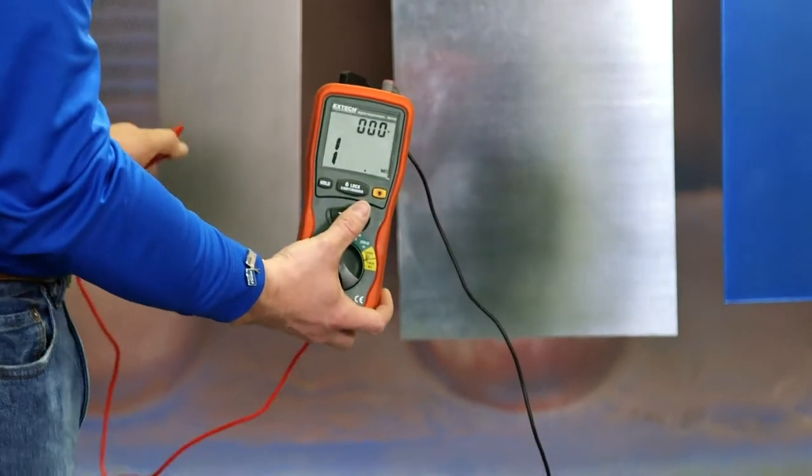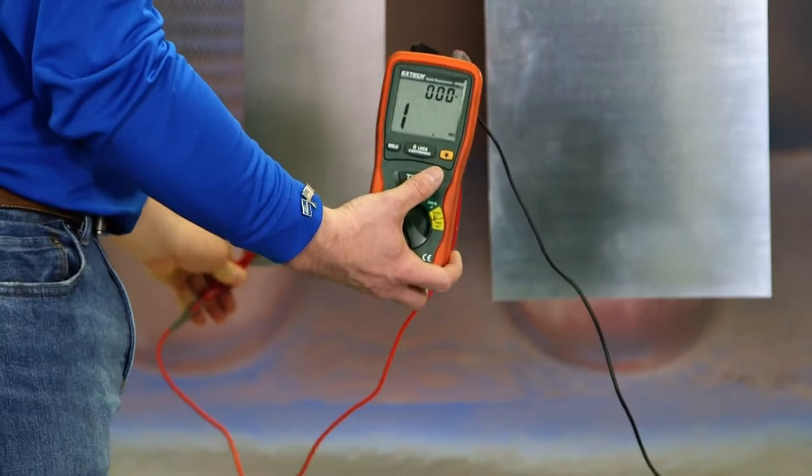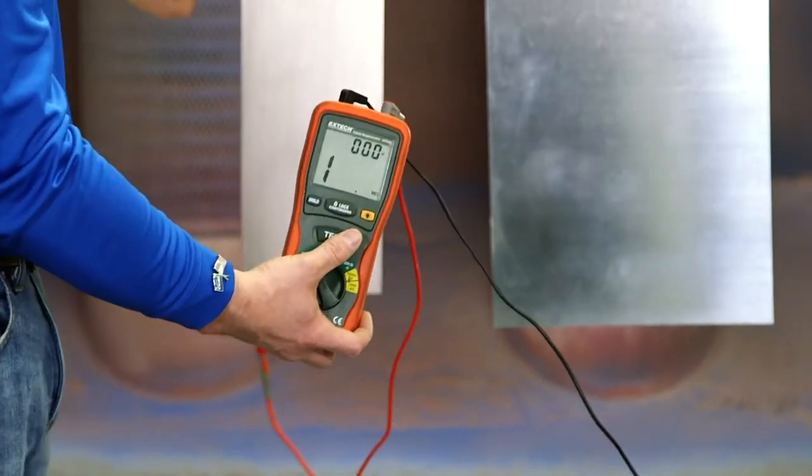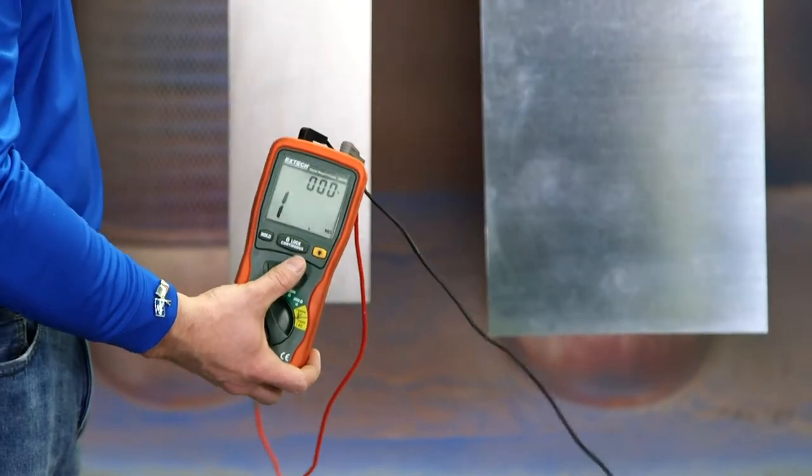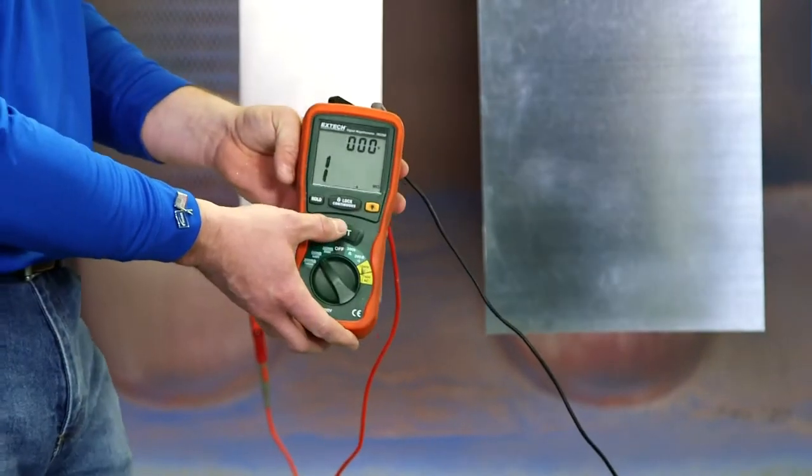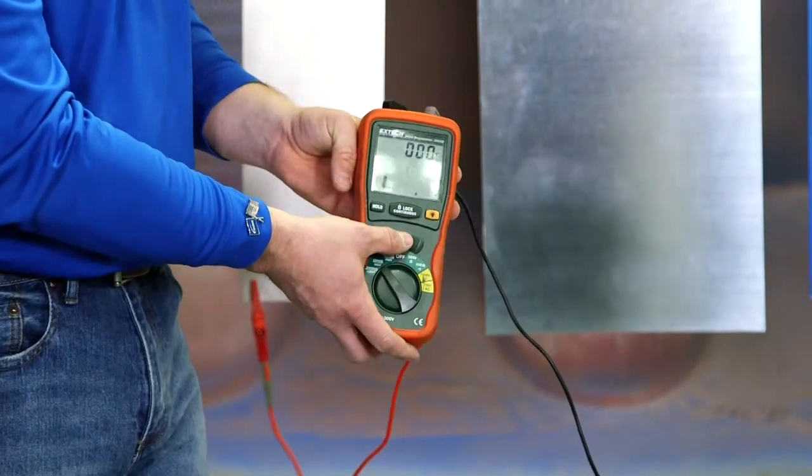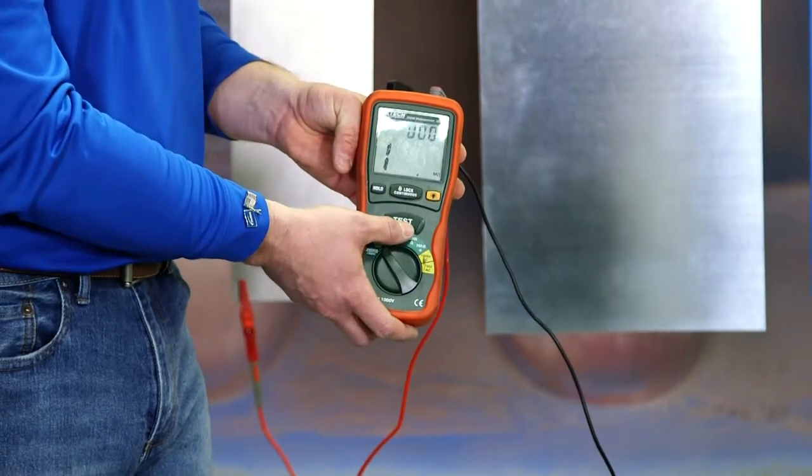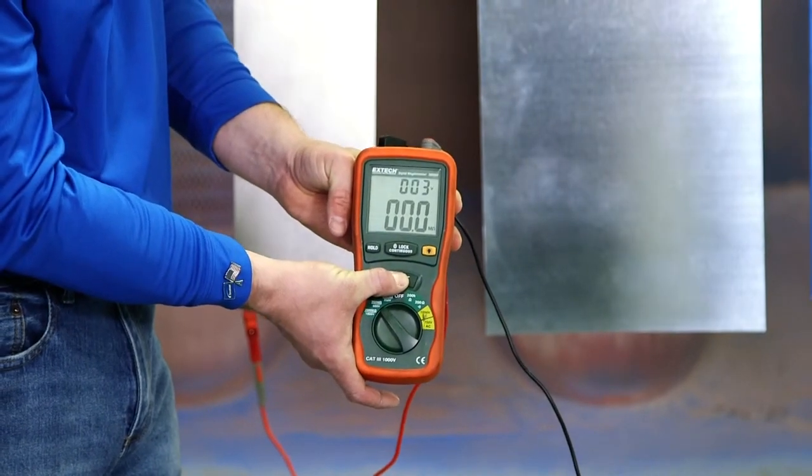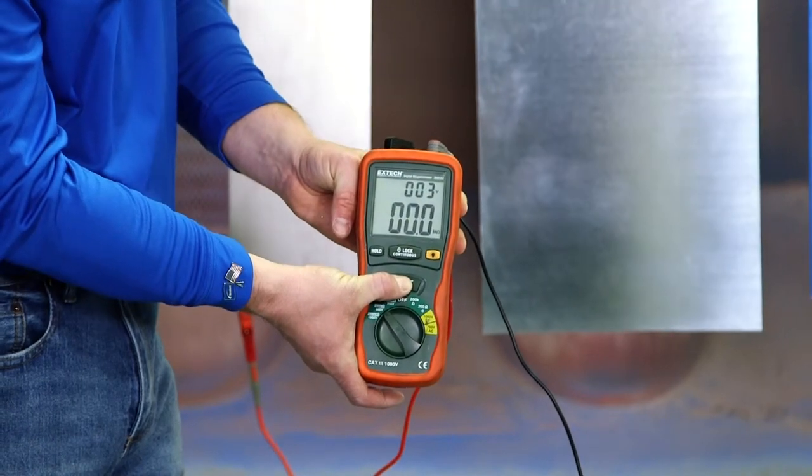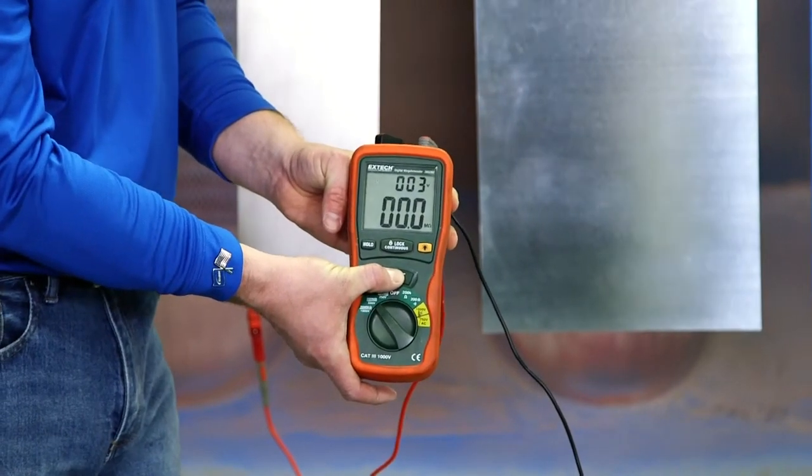To test this we'll clip this to the part. Since this is an unfinished piece of metal with clean hooks, this should test correctly. To show a true ground it needs to be less than one mega ohm. The test shows zero so it passes the grounding test.